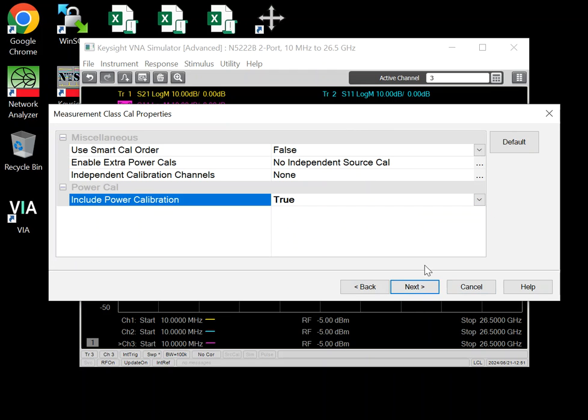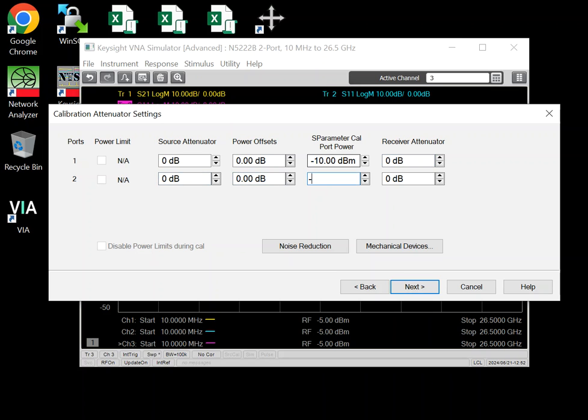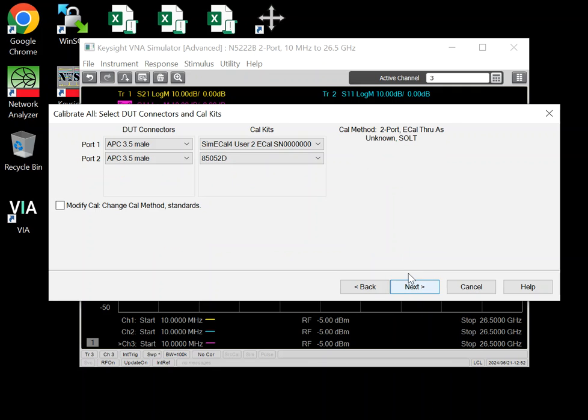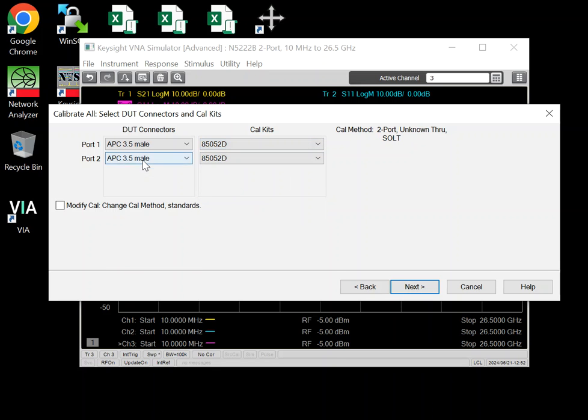And I'm going to say I don't need a power Cal. Actually, let's set this to false. You want to set the power menu. Power, let's say minus 10. Actually, for mechanical Cal, zero is fine.